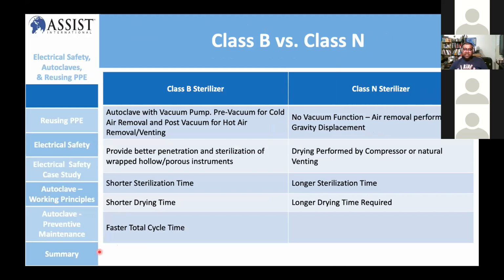So class B versus class N. When you talk about class B, sterilization is a vacuum thing: autoclave, vacuum pump and pre-vacuum for cold air removal, and post-vacuum for hot air removal and venting. That's how it works on class B, and it provides better penetration and sterilization for wrapped, hollow and porous instruments. The sterilization time is shorter, the drying time is shorter, and the total cycle time is fast. So this is the advantage of class B sterilization.